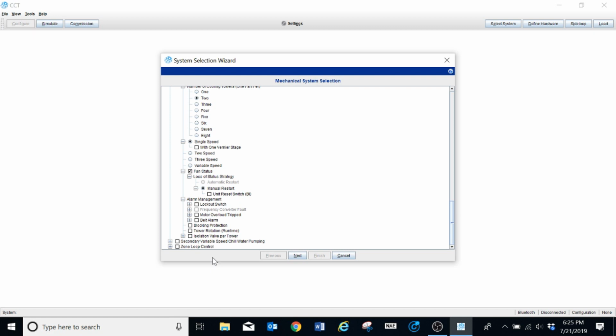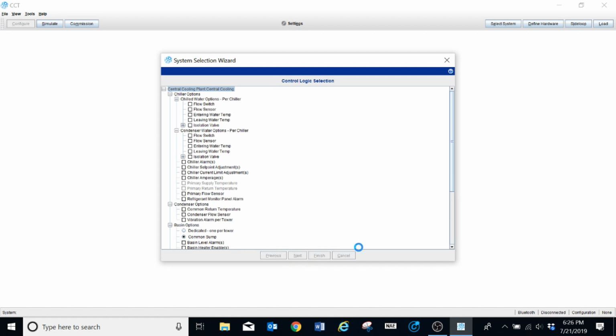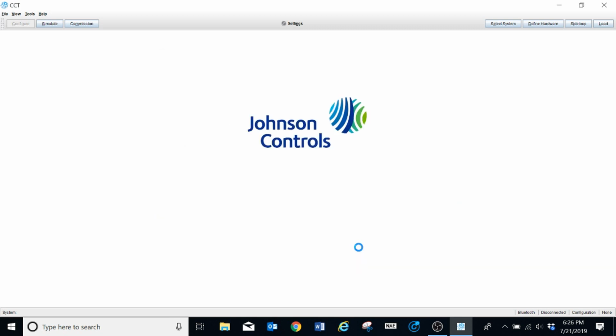with an FAC controller. I don't know if any of you guys are familiar with those. I did a video that highlighted a little bit about those FAC controllers. They basically are an FEC controller on an adapter plate that allows you to plug them directly into a DX9100 back panel. In a situation like that, you should be able to replace a DX9100 with one of those FAC controllers. What you will run into, however, depending on how your system is configured, is that you're going to need to sit down with your drawings and your wiring sheet to get everything figured out the way you need it.